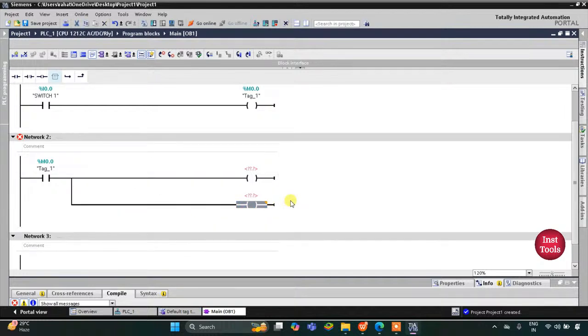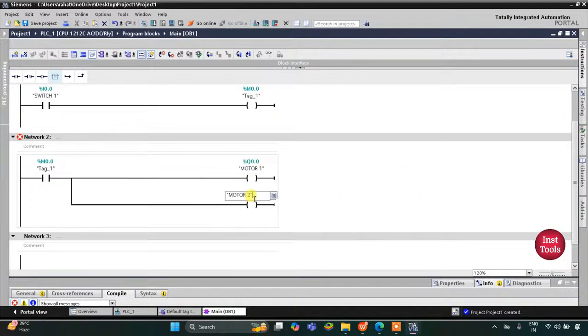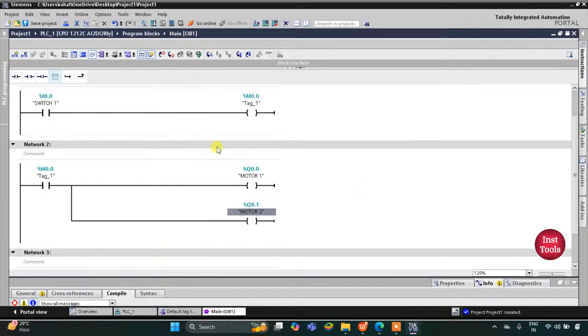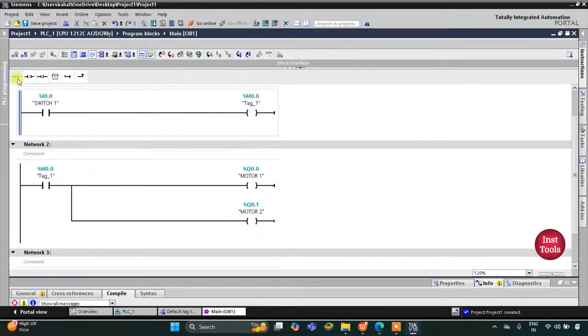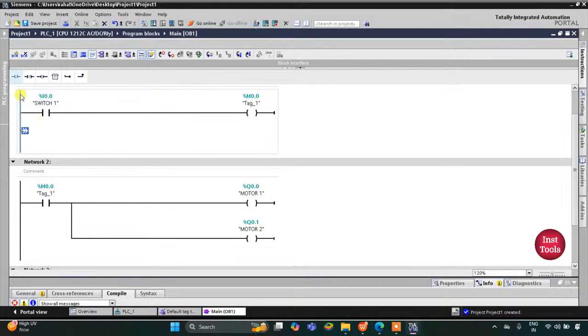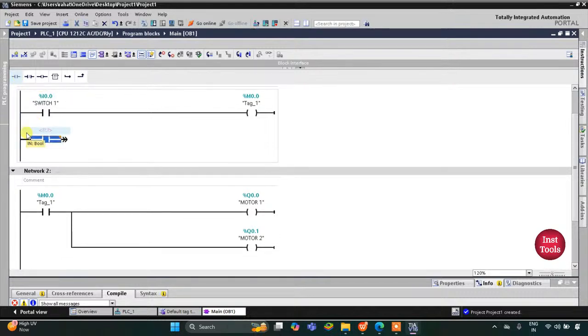I use the shortcut Shift+F8 to open the branch, and Shift+F7 to insert a coil. This coil will be for Motor 1 and this coil will be for Motor 2. When Switch 1 is pressed or turned on, M0.0 gets true, and when M0.0 gets true, Motor 1 and Motor 2 turn on. But when Switch 1 is turned off, M0.0 turns off which will turn off the motors. To keep them on we need to latch, so I will open the branch with Shift+F8, insert a normally open contact with Shift+F2, and then close the branch. I will assign address M0.0 to this normally open contact as a memory bit.